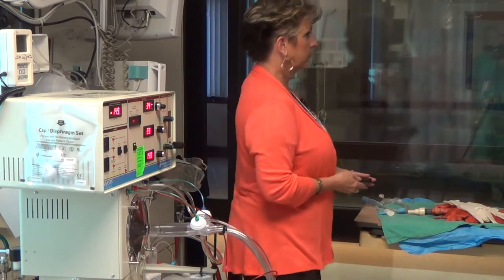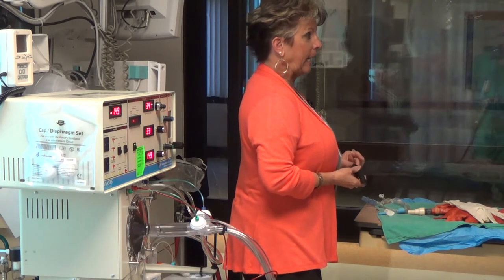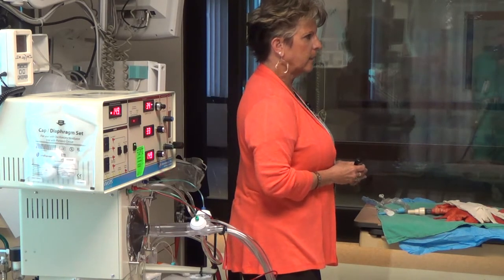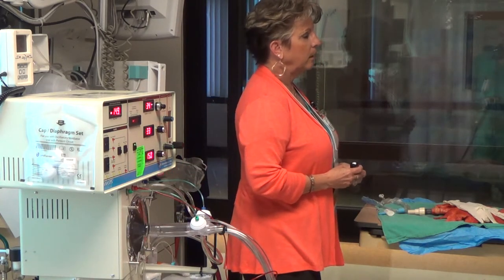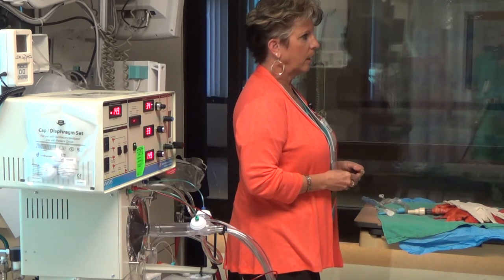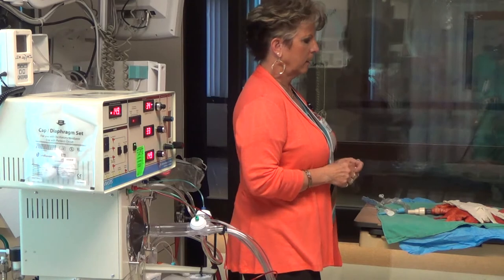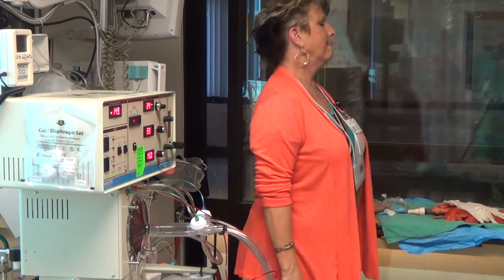So how many years have you been working with the oscillator? I was going to ask you last time. It came out in '91, and I started working with it about then. Have you ever seen a hole in the diaphragm? Yes. Is it back here? Uh-huh. That happened to us just a couple of months ago. Was it on the patient a long time? I don't know how long, but I got called by another therapist, like emergency, come down, troubleshoot, put some more eyes on it. And it just made a funny sound. It was really weird. It sounds floppy. It did, and it just dropped the pressure by a lot.